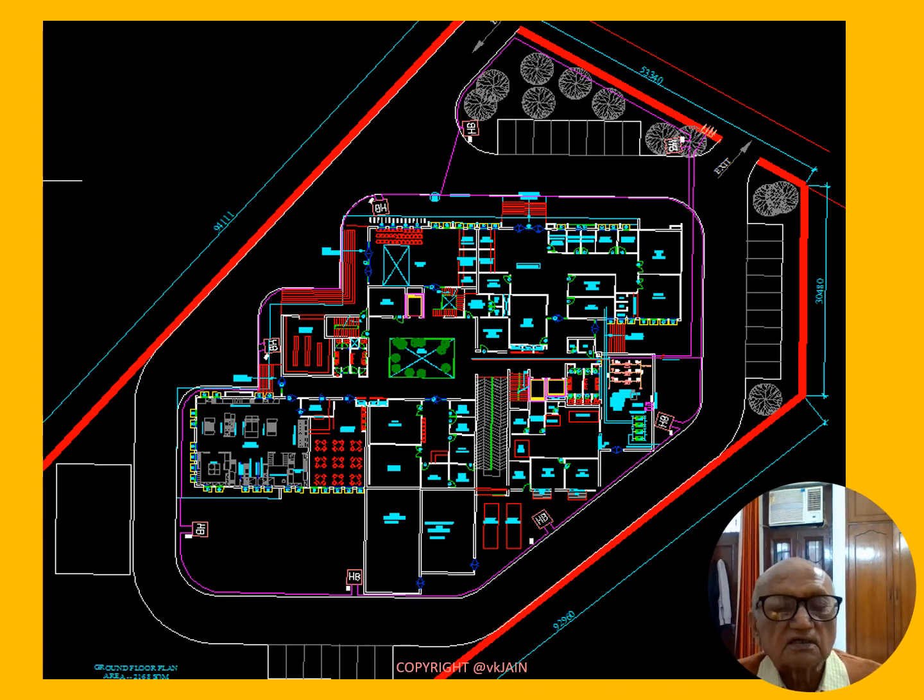Friends, in this slide, I am showing a real life campus of a healthcare system, a medical college, 100 bedded at some particular place, in which you can clearly see the yard hydrant system provided in a ring main fashion in the campus, and the standpipes denoted by HB are strategically located so as to protect each and every building in the campus.